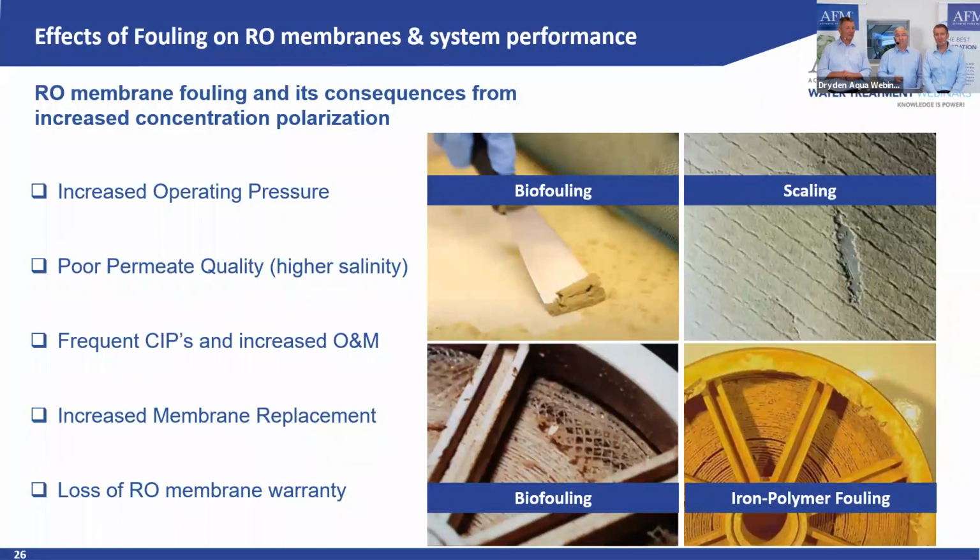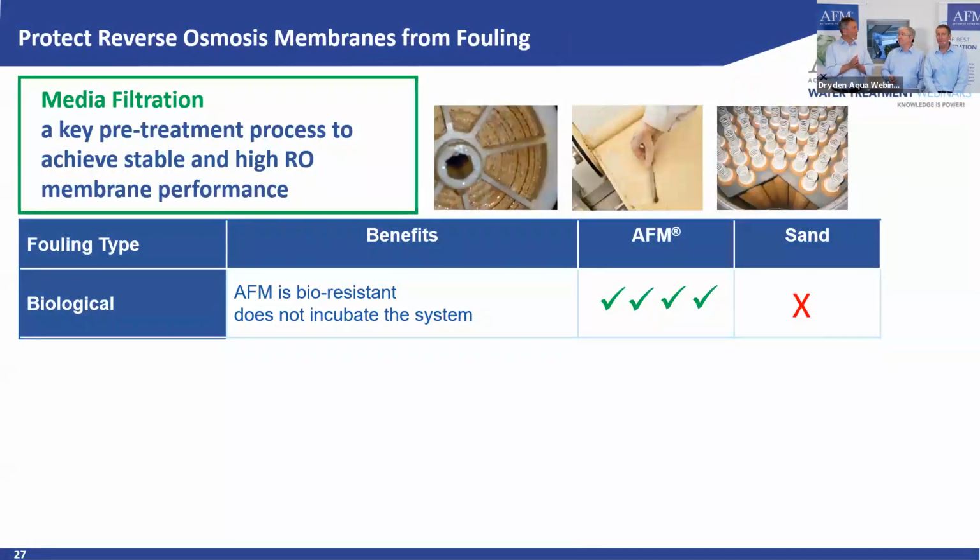But guys, maybe we make the solution a little bit better. What's the last point? Loss of RO membrane warranty: if you reach this point, you probably lost your membrane warranty in the meantime. That means all the nice membrane replacement you have agreed with your supplier is lost. So again, higher energy, and loss of money because you need to pay much more for your membrane elements yourself. It gets really expensive. And actually more important, downtime. Big desalination plants, if they don't operate, cost more money for the downtime. So we now split the RO world into two groups, right? The operators who will love us because their costs will go dramatically down, and some of the suppliers who will not love us. Maybe the EPCs and OEMs will love us, right?